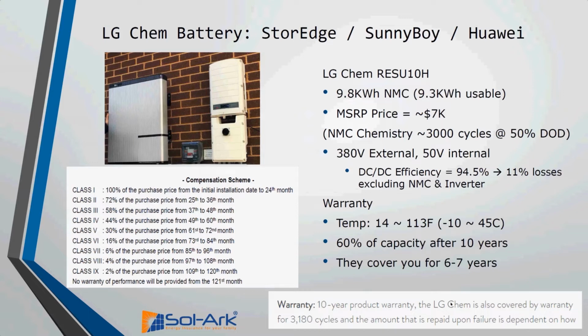Also, temperature affects the warranty. You have to keep it within the operating temperature range, and capacity decreases over time. At 10 years, you can expect only 60% of your capacity. Realistically, all this combined means they're really only going to cover you for about 6 or 7 years.